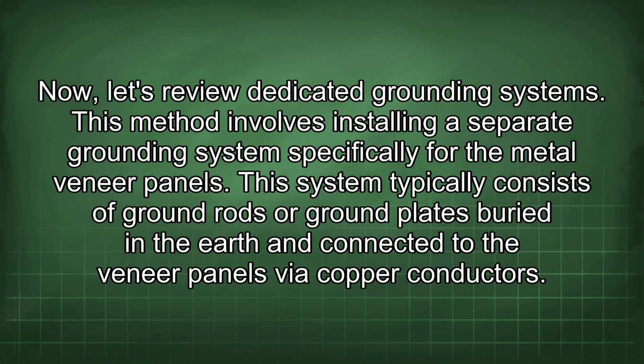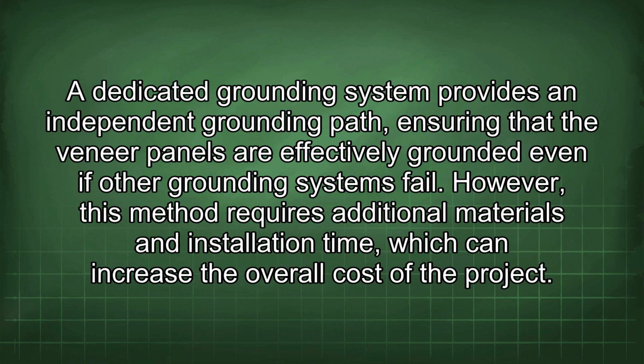Now, let's review dedicated grounding systems. This method involves installing a separate grounding system specifically for the metal veneer panels. This system typically consists of ground rods or ground plates buried in the earth and connected to the veneer panels via copper conductors. A dedicated grounding system provides an independent grounding path, ensuring that the veneer panels are effectively grounded even if other grounding systems fail.